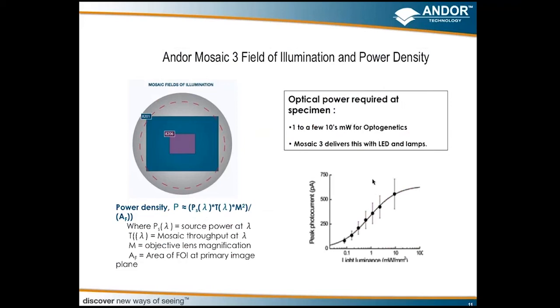To hit the point home, with the Mosaic 3 and the DMD, imagine a chip with hundreds of thousands of mirrors being illuminated by a light source. You get a loss of power because the fraction of power at any spot depends on what's coming off an individual mirror. But we've done a lot of work looking at power density, and we can get up to 50 or more milliwatts per millimeter squared with the X-Cite LED at common optogenetics wavelengths. So the Mosaic 3 delivers more than enough power with LED, arc lamp, or metal halide for optogenetic techniques.